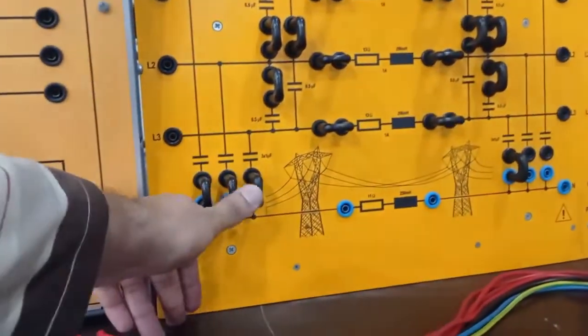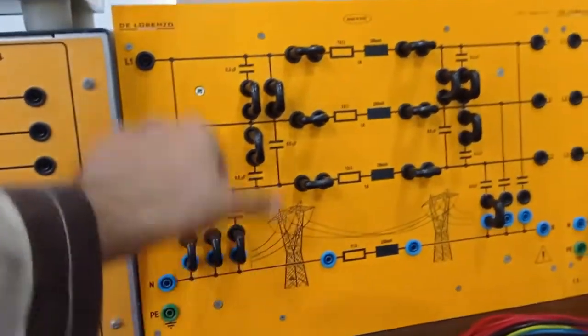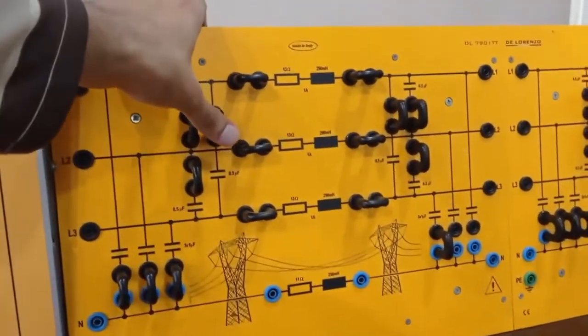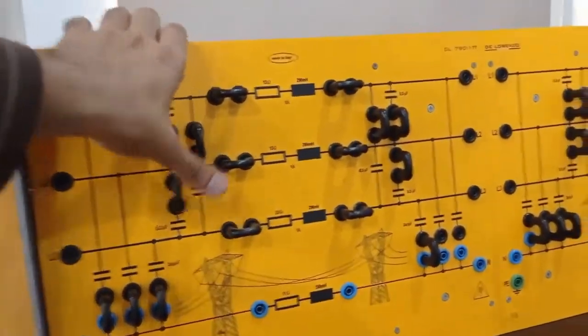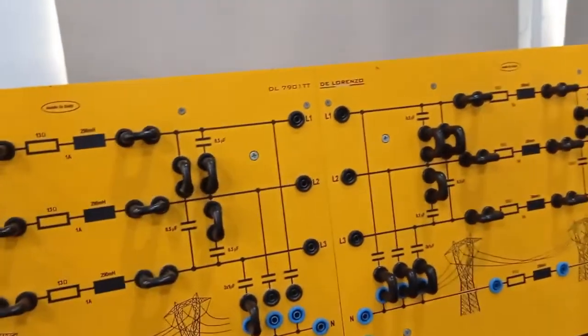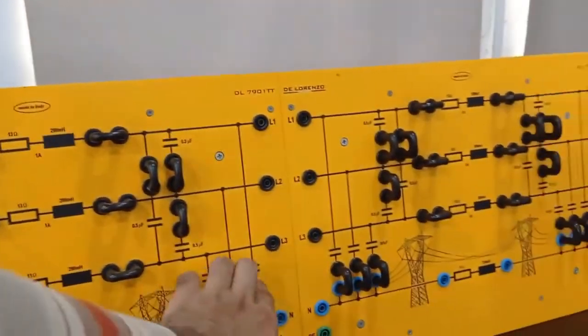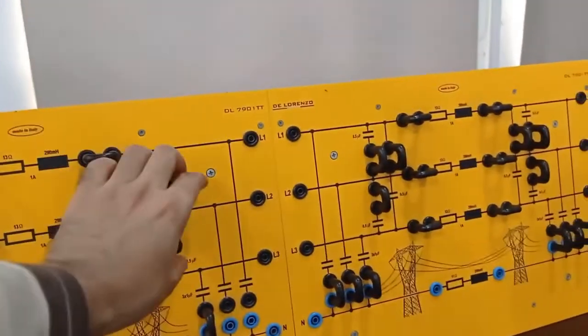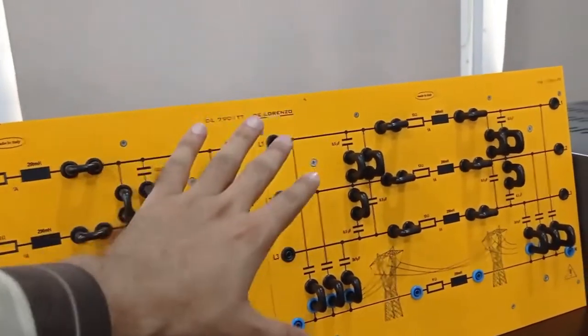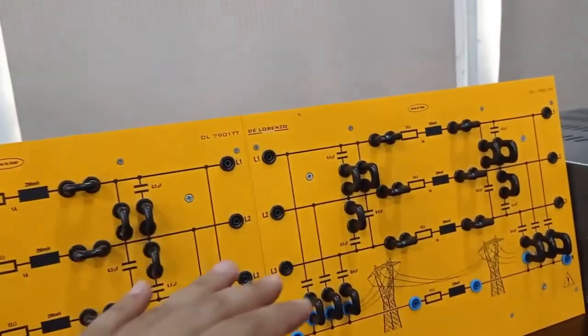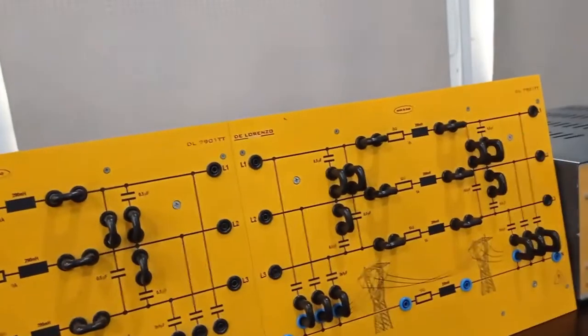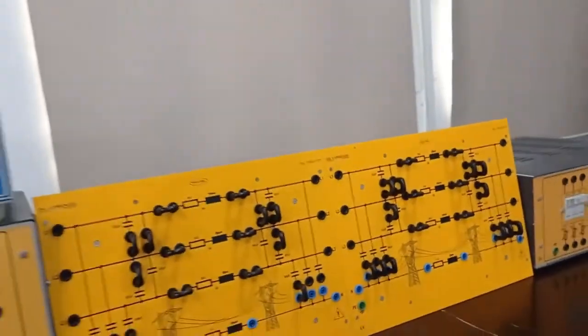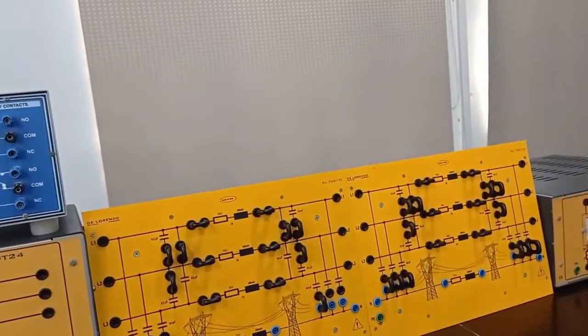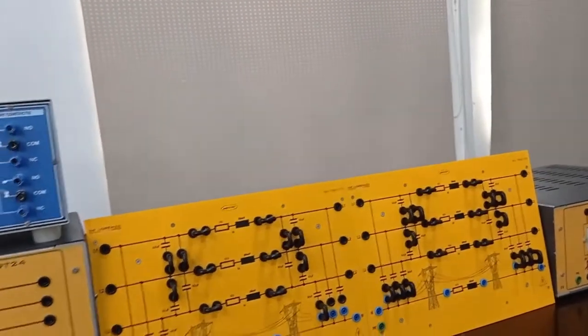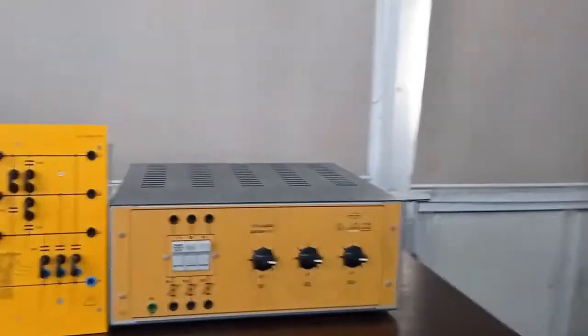So make sure that it is working in proper condition, so push pressure on all these shunt connectors so that they are properly inserted. As we can see here in this particular example, these are not properly inserted. So make sure all these 6 line to neutral and 6 line to line capacitances are in the system when you are performing with capacitor, and remove all these capacitances when you are performing the experiment without capacitance. Insert the capacitances properly. Then we have a resistive load.